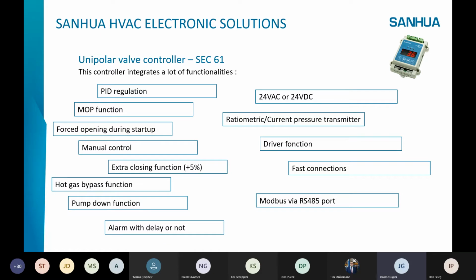A driver function is where you don't use the intelligence of the algorithm of the SuperVit, you don't use the algorithm from the SEC. You use your own control, your own algorithm, and you just send an analog signal to the controller, and the controller converts this signal to a stepper motor signal. We have already this fast connection because we use XHP connection to go fast during production on the production line, and we have also a Modbus port to communicate with other controllers or with the supervision. So all the parameters are accessible in read and write.